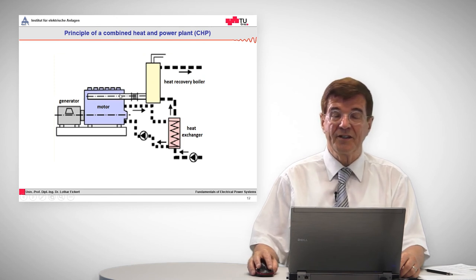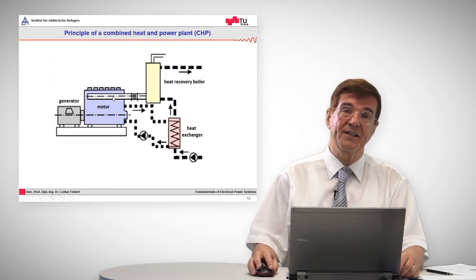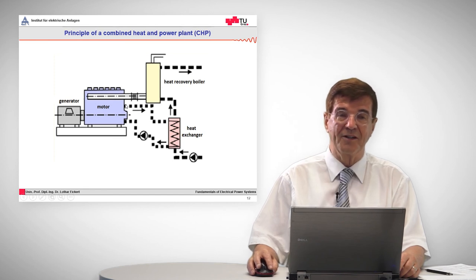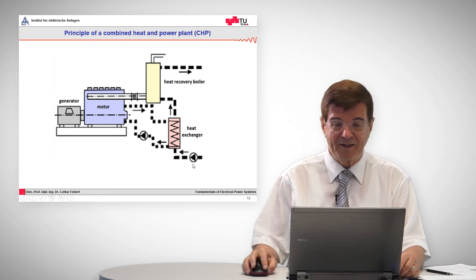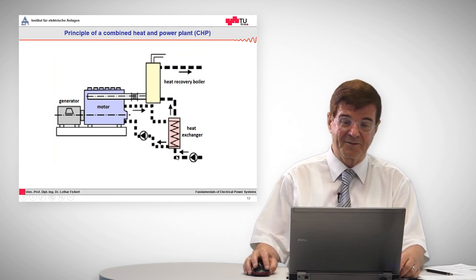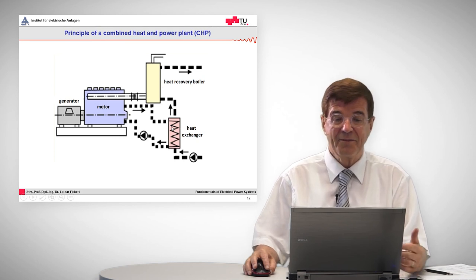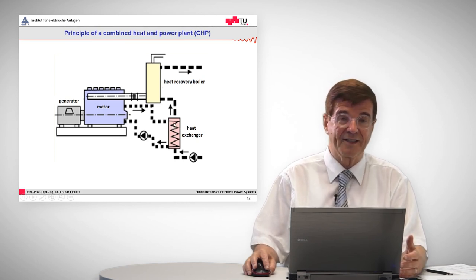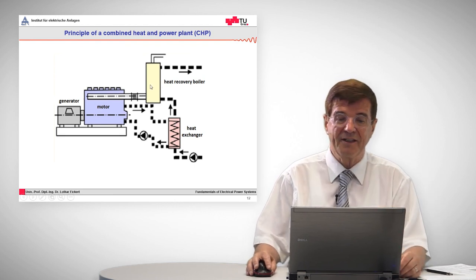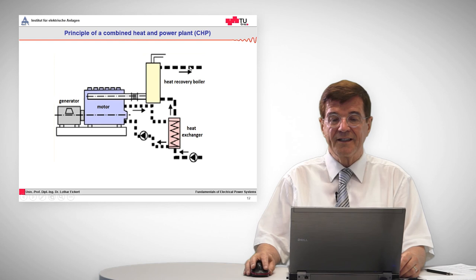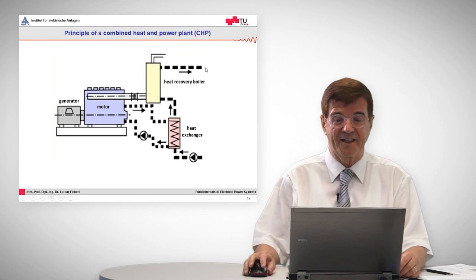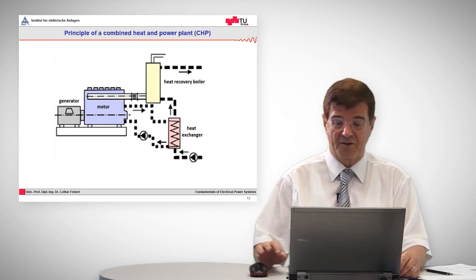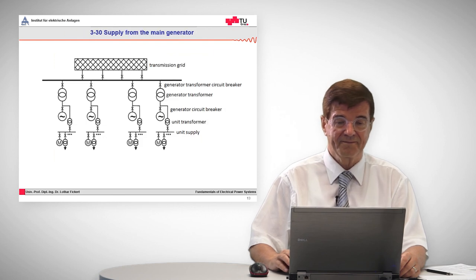And it is not only the hot exhaust fumes that are used, but also the oil which is heated in such a motor. This is used in a heat exchanger, where the water, when it comes from the customer or enters the circle, is first warmed in a first step by using the heat of the oil, the energy of the oil. Then it takes more energy in this heat recovery boiler, and then it goes back into this heating cycle, for example, to heat homes or houses or something like this.